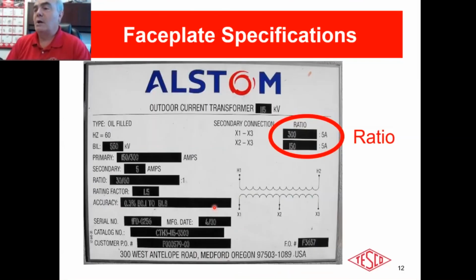All right, let's talk a little bit about the faceplates. So everybody's probably seen a faceplate on a transformer, but you may or may not have paid a whole lot of attention to it. It is a very important piece of the puzzle. So first of all, we picked one that we had downstairs. This is an Alstom transformer. There's a number of very good transformer manufacturers. In general, in our industry, every manufacturer, unfortunately, including even our competitors, is a very good manufacturer. If you're in this industry, utilities expect the best. There's really no tolerance in our industry for anything less than the best. So if anybody's been around for a while, there is a reason, and that's because what they produce and what they supply to the industry is a good quality product.